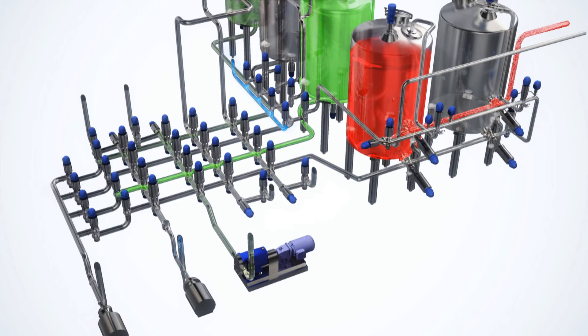It may seem unnecessary to equip the flat bottom tanks with both mix proof tank inlet and outlet valves. In this case, the valves enable the tanks to be used as buffer tanks, filling and discharging them at the same time.